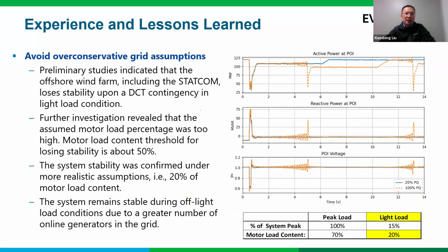All right. Just before the commissioning test, a study showed that the STATCOM and the wind farm would be unstable upon a double circuit contingency at a light load condition. This would result in a significant generation curtailment at pre-contingency, which is unacceptable for the farm. Unfortunately, further studies revealed that the instability only occurs when the motor content of the grid exceeds 50% of total. But in reality, the motor load content is only about 20% per information given by the local TO. So this is far below the stability threshold of 50% motor load.